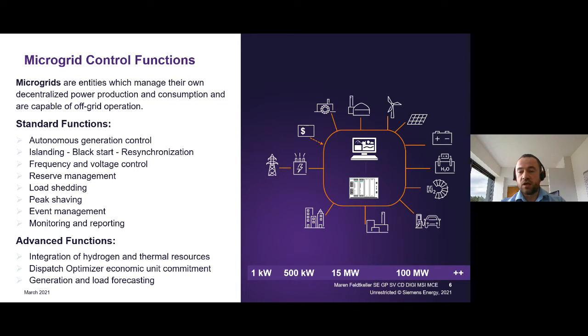Load shedding functionality is implemented by a microgrid controller when there's a certain event in a microgrid - for example, when a generator falls out, non-essential or non-critical load is shed in order to keep stability. Data archiving and event management, all of these functions run in the connected small SCADA system with the microgrid controller.